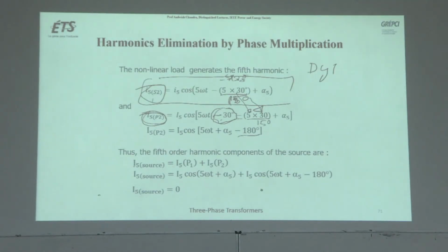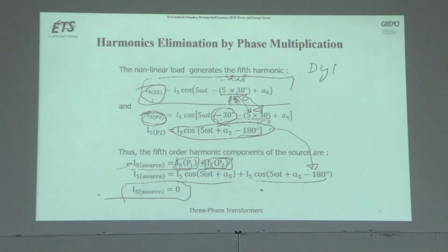Okay, so the source current, 5th harmonic, from the first transformer and from the second transformer: from the first transformer, the DD0 transformer, there was no phase shift, and the second transformer, DY1, has minus 180 degree phase shift. So the 5th harmonic is cancelled, right? So this is the advantage. Instead of using a second DD0 transformer, we are using a DY1 transformer, which is cancelling the fifth harmonic.